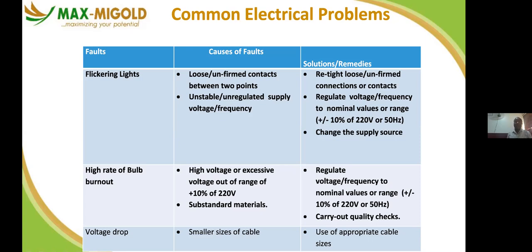It could be substandard materials that have been used for your installation. It could be the switch or the lamp holder itself. What do you do? You regulate voltage and frequency to normal values or range. So you check the frequency as well. It could be that the speed of your generator is too high. So you carry out a quality check and resolve.